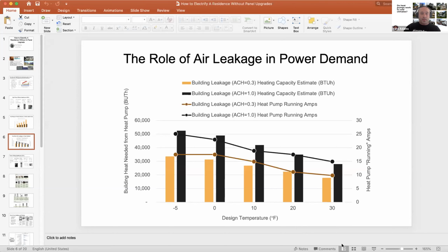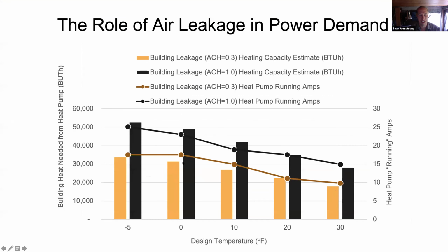I'm showing a slide to help illustrate the role of air leakage in heat pumps. This covers -5, 0, 10, 20, and 30 degrees Fahrenheit. In black you see the energy demand. At an air exchange of 1 per hour, measured at actual atmospheric pressure, not blower door high pressure, that's very leaky, like a 1920s house. You can see the decrease in power demand and heating load as you weatherize or insulate down to 0.3 ACH.